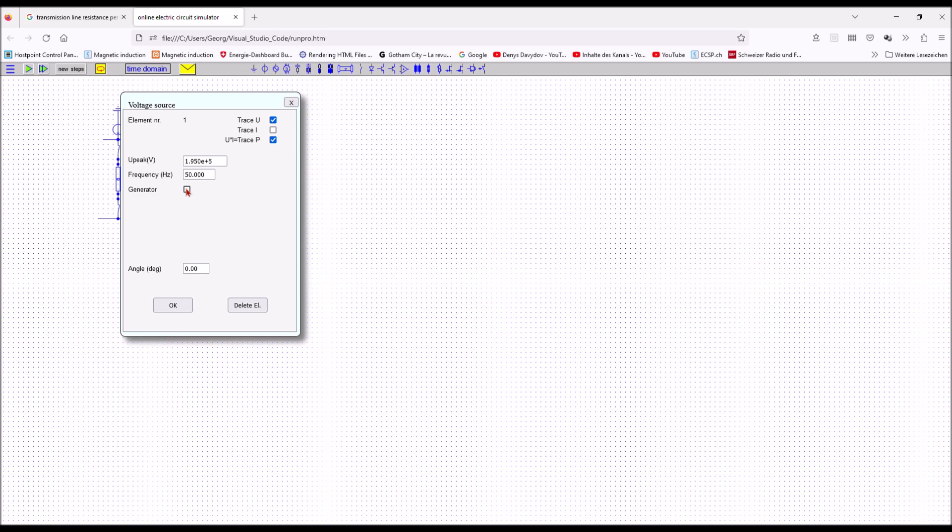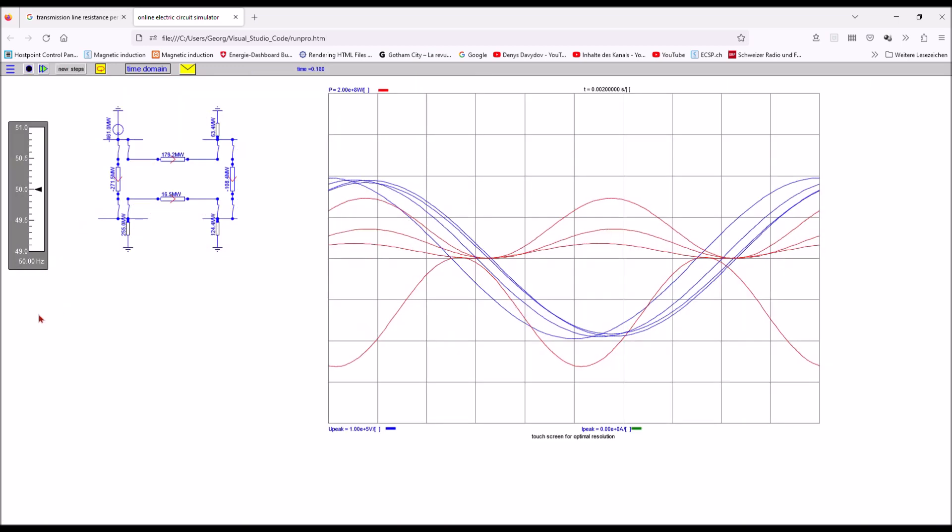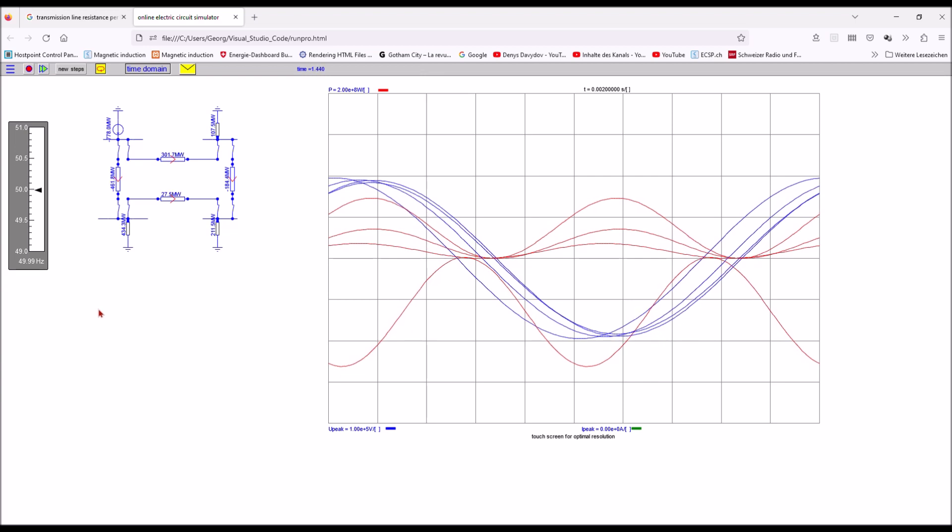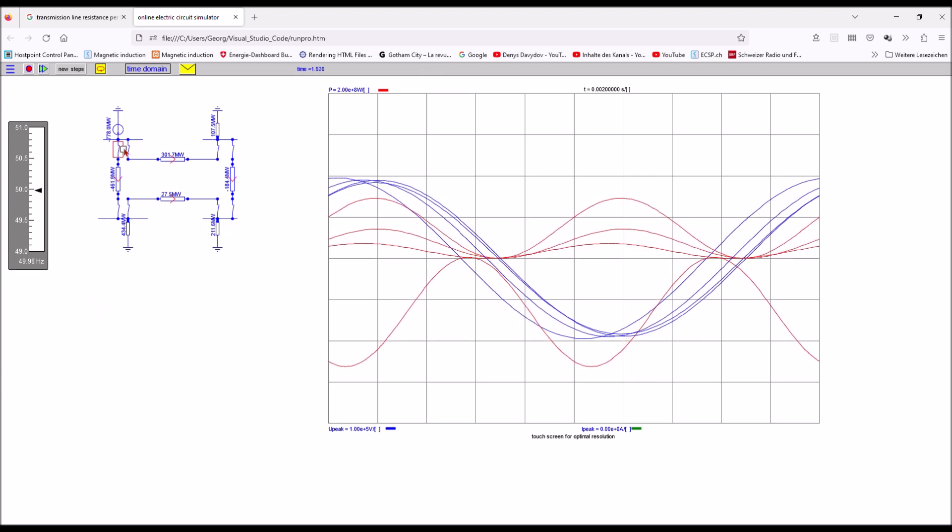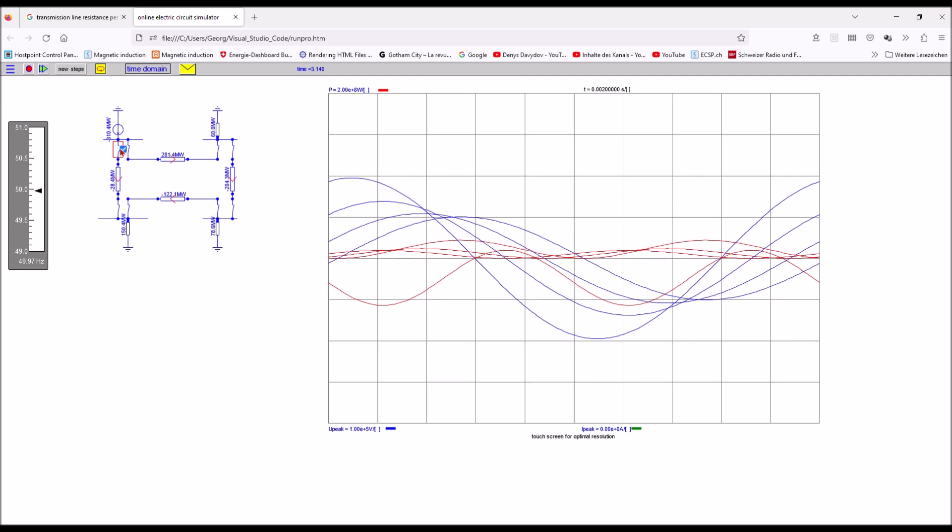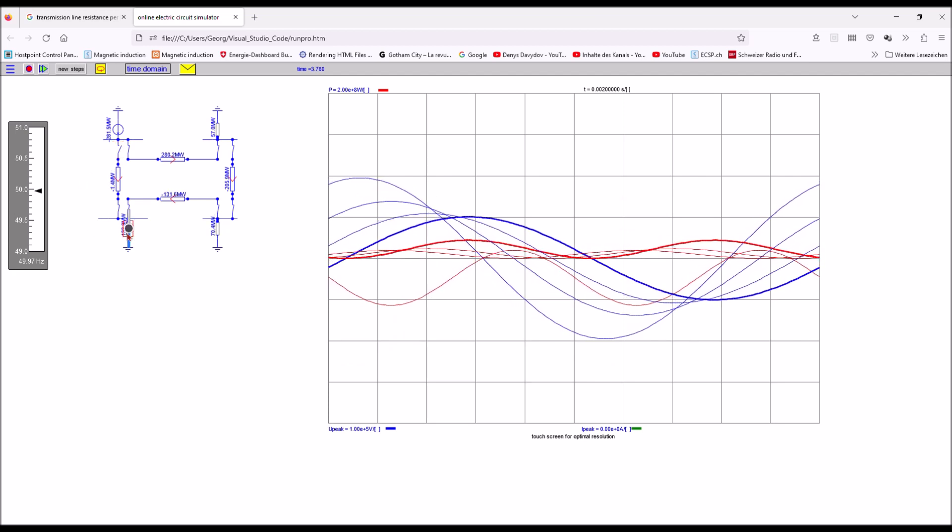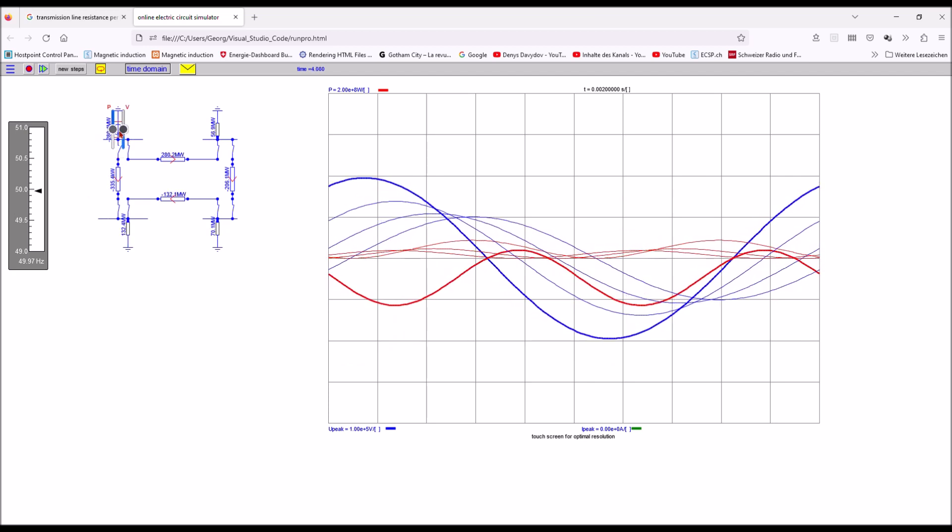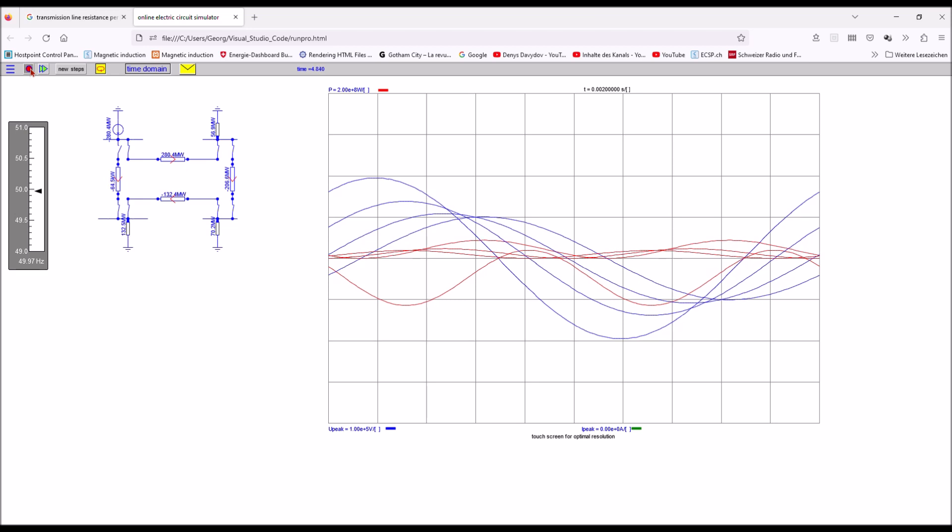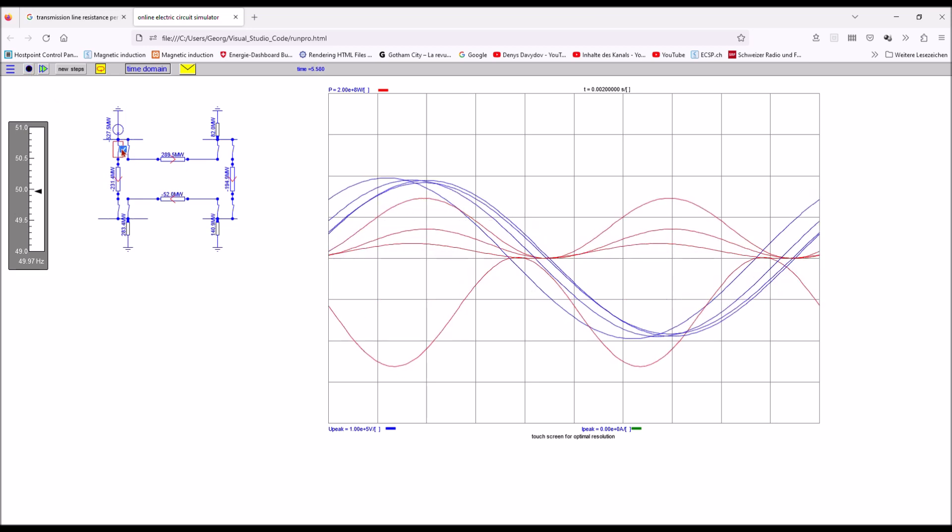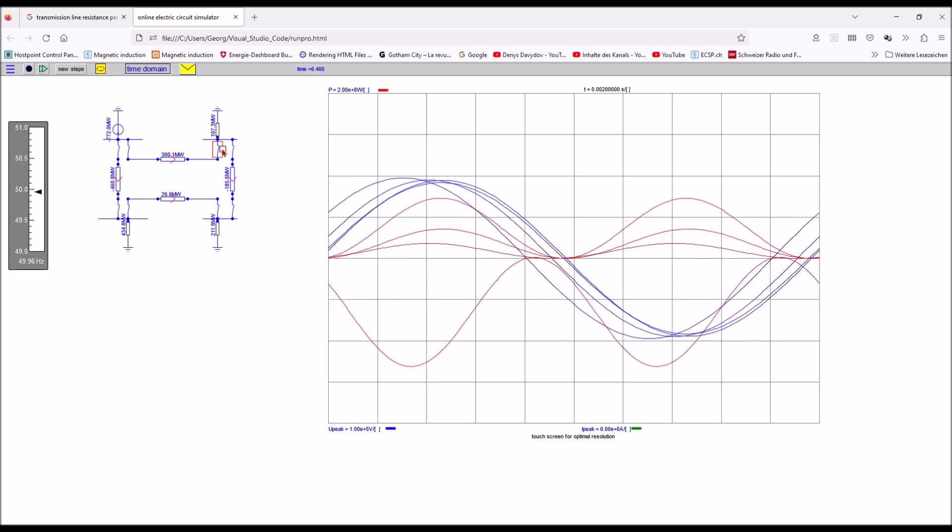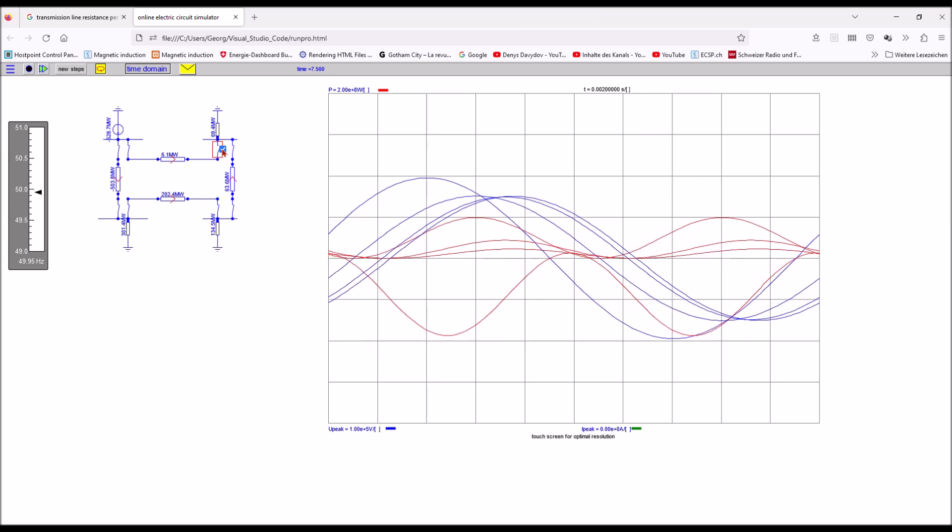In order to get these values we need at least one of the sources being set as a generator. To imitate the slack bus performance I entered a very high power value. You can observe that if one of the lines is taken out, for example due to a lightning strike, it has a huge impact on the voltages at all the loads. Thus the voltage stability of this system would immediately collapse.